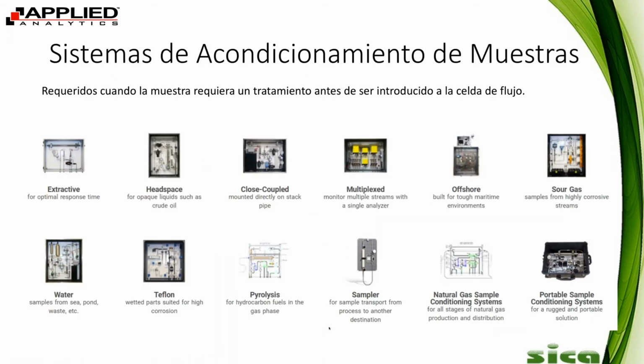Here you can see a bunch of different images of sampling conditioning systems. Basically, we're controlling the sample's pressure, temperature, density, and phase. Say it's a natural gas sampling system. Sometimes we need to use aromatic traps to get rid of the aromatics, so there's no cross sensitivity with the H2S measurement, anything like that. There are a few drawings in there, and then some actual images. But they're all sampling conditioning systems which we offer with all of our analyzers.